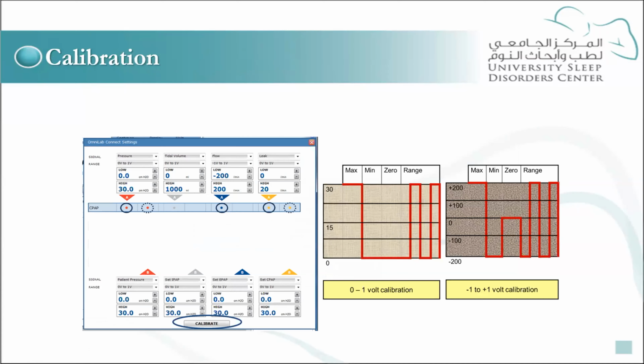Last but not least is the calibration. It's very important to properly calibrate the signals you will display on your polysomnograph. On the left side you see what you have on your screen. For instance, if you are doing CPAP titration, different signals can be displayed and you need to titrate or calibrate them.